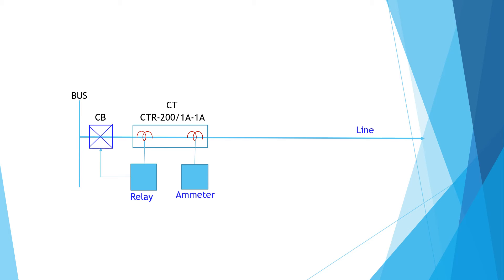The current ratio is substantially constant for given range of primary current and phase angle error is within specified limit. VA rating, that is burden of current transformer, is very small, in the order of 15 VA, 30 VA, etc.